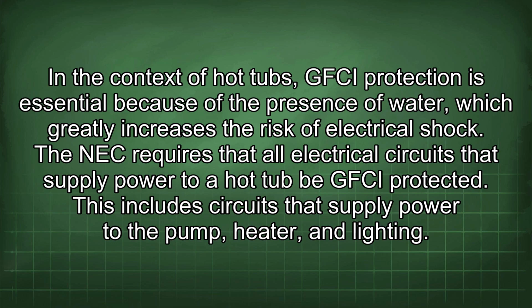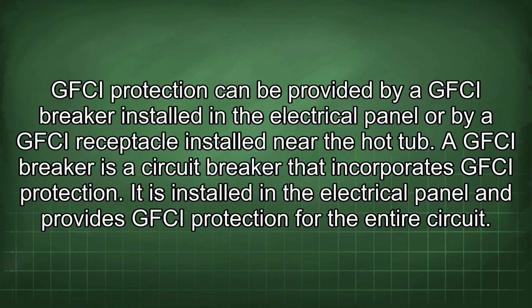The NEC requires that all electrical circuits that supply power to a hot tub be GFCI protected. This includes circuits that supply power to the pump, heater, and lighting. GFCI protection can be provided by a GFCI breaker installed in the electrical panel or by a GFCI receptacle installed near the hot tub. A GFCI breaker is a circuit breaker that incorporates GFCI protection.